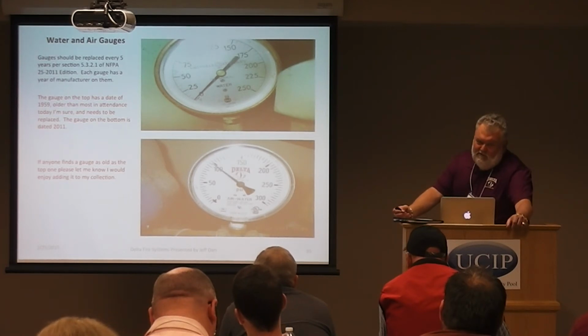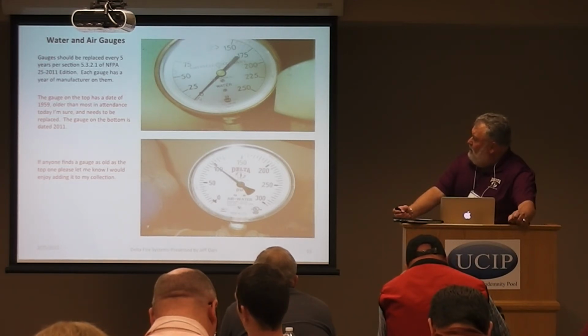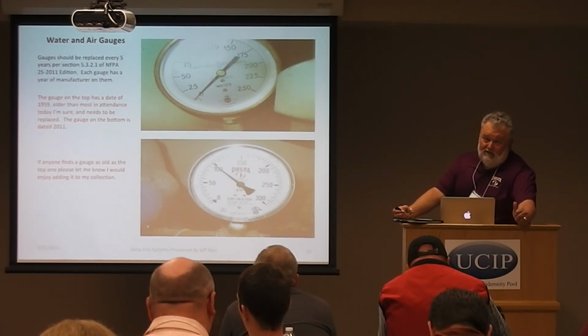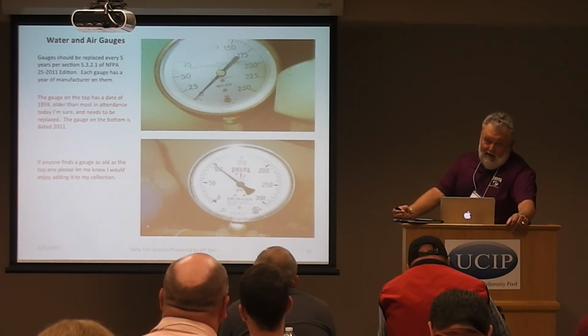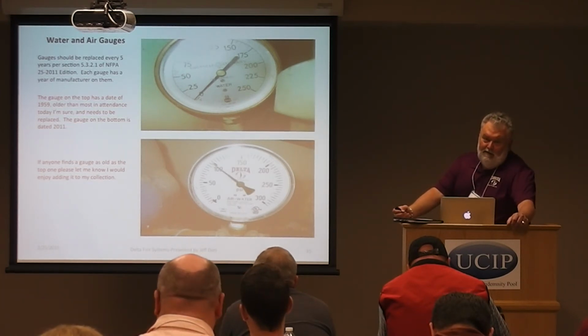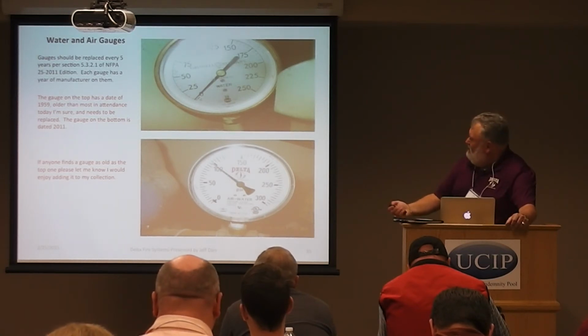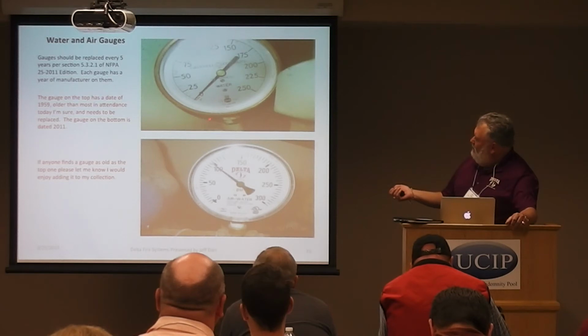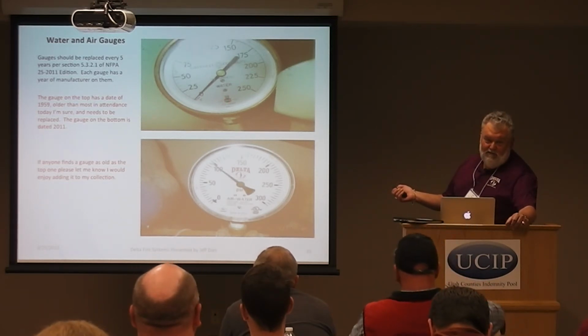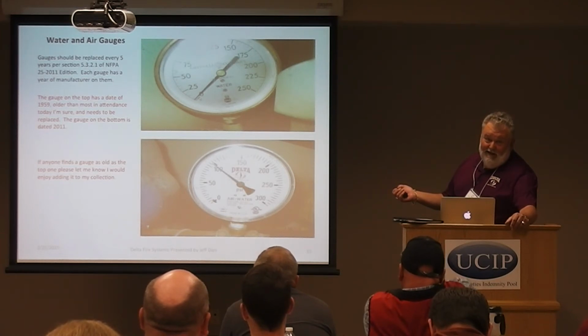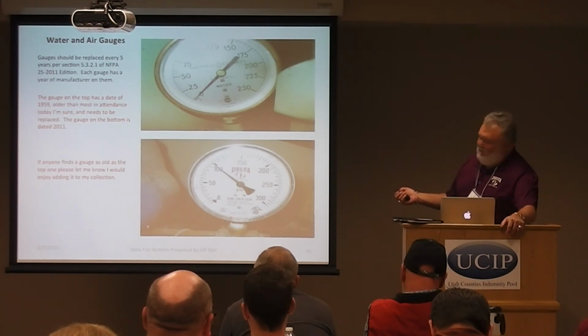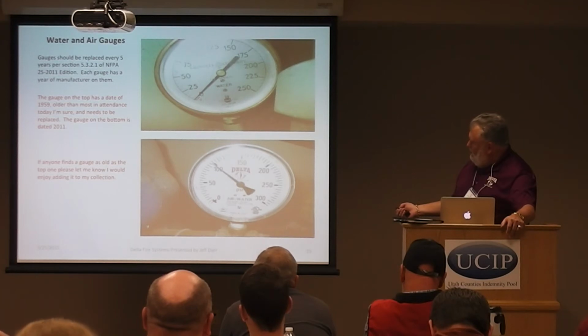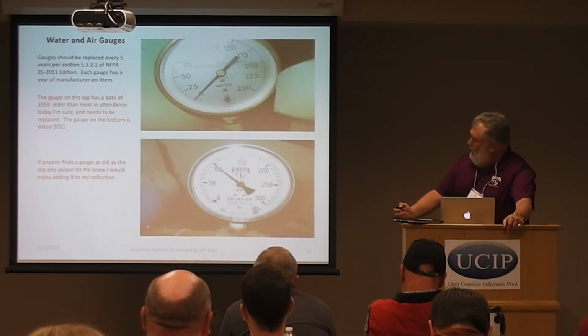Okay, here are some examples of water gauges, and per 5.3.2.1 of NFPA 25, a gauge should be replaced every 5 years or sent back in and certified and recalibrated. It's cheaper to replace a gauge than it is to have it recalibrated because we have to send it to the manufacturer. I'm not sure if you can see this or not, but right here on this gauge is 1959. That gauge definitely needs to be replaced. I'm sure it's older than most of you in here. Unfortunately, I'm older than that one. This one, that year is right here, 2011. So that one's coming up where it'll have to be replaced.